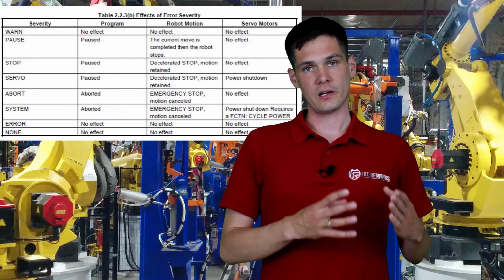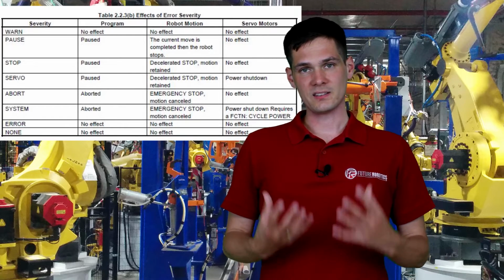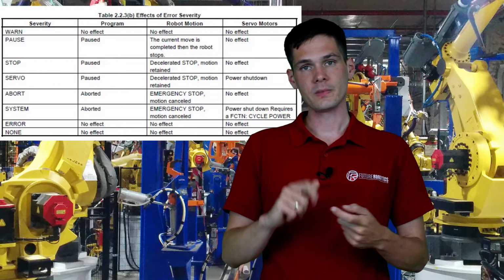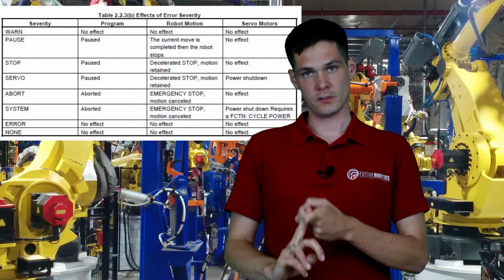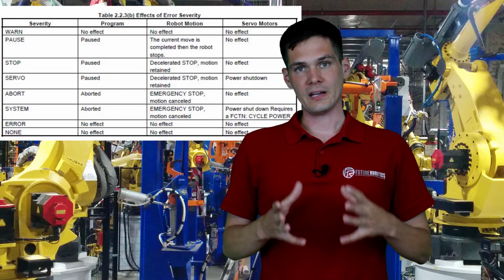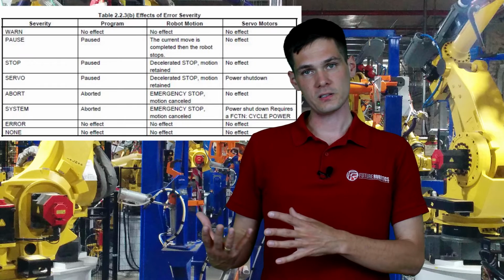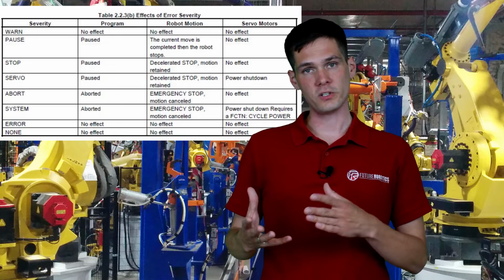There can be only a warning or there can be an e-stop. Stops affect three things: one is the program execution, second is the motion execution, and the third is the robot servo. Depending on the error severity, the robot behaves differently on a different alarm. We're going to get into that more deeply during the exercises. For now, I'm just trying to tell you the basics.